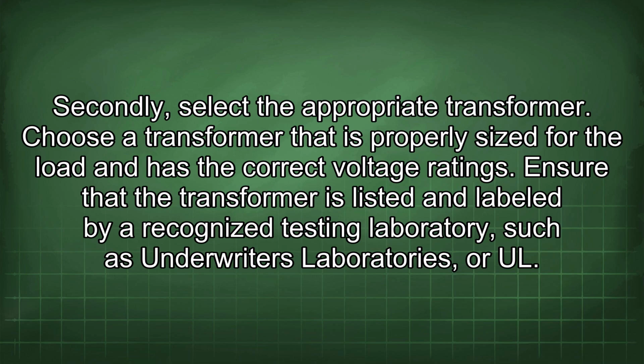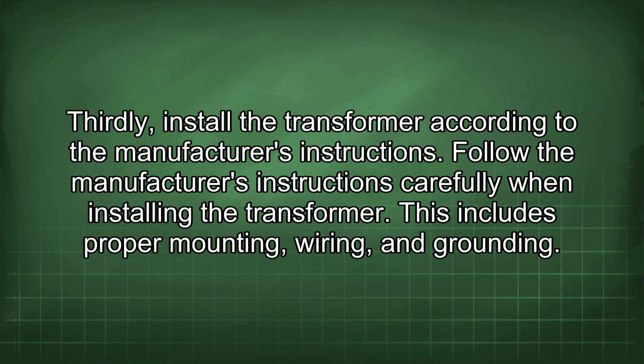Secondly, select the appropriate transformer. Choose a transformer that is properly sized for the load and has the correct voltage ratings. Ensure that the transformer is listed and labeled by a recognized testing laboratory such as Underwriters Laboratories or UL. Thirdly, install the transformer according to the manufacturer's instructions. Follow the manufacturer's instructions carefully when installing the transformer. This includes proper mounting, wiring, and grounding.